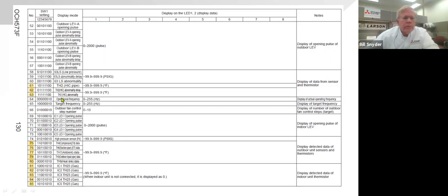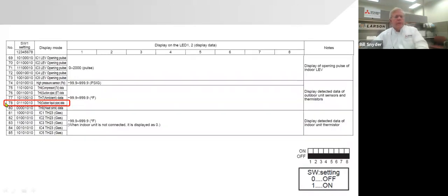I can't see TH3. It's got to be right in front of me here. Maybe it's on another page. Oh, right here, TH3. Number 78 is TH3. So if I turn switch 1 off, 2, 3, and 4 on, and the last from the right on, it'll actually display on that little segmented display the actual temperature it's seeing. If it sees a negative 99.9 or a 999.9, it's shorted or open. Otherwise, you can actually read the thermistor temperature right on that display.